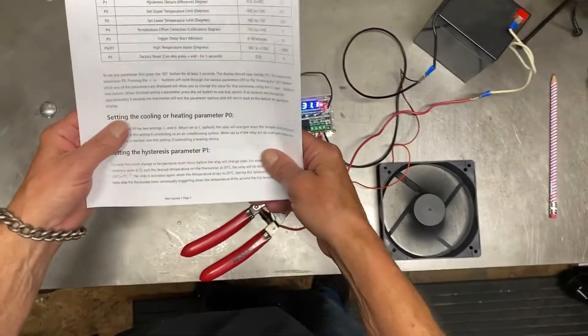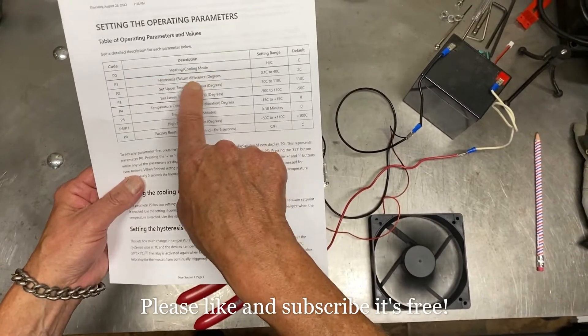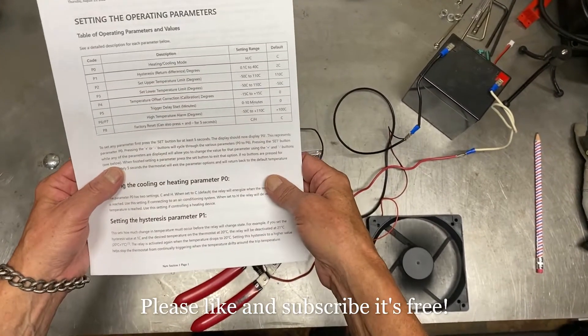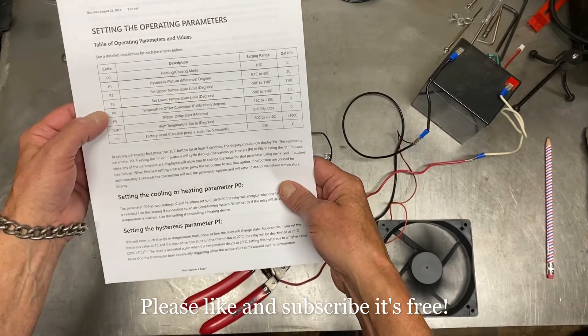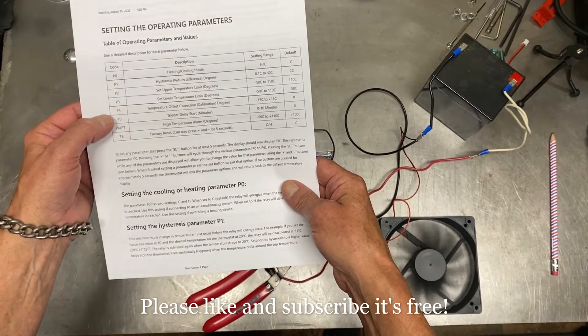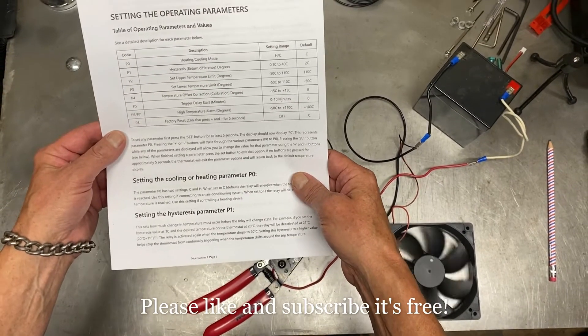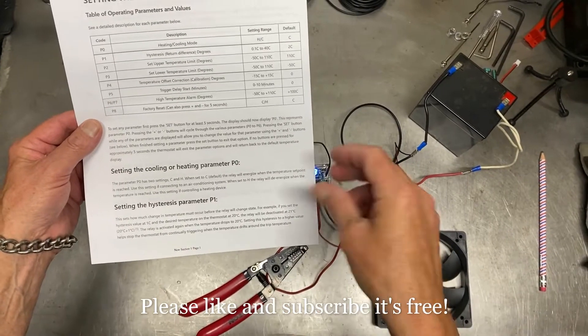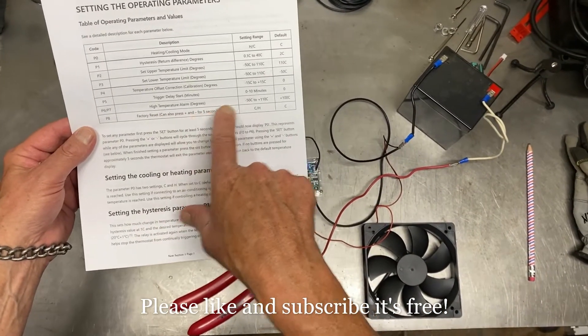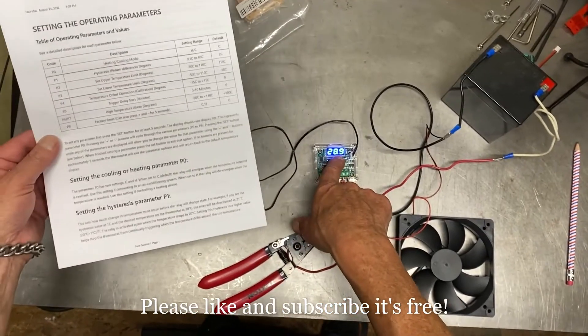There are different settings and parameters you can configure. P0 is heating and cooling mode, P1 is hysteresis, P2 is set upper temperature, P3 is set lower temperature, P4 is temperature offset, P5 is trigger delay start in minutes, and P6 and P7 are high temperature alarm and degrees. Not all of them have all these codes — this particular one only goes up to P6.